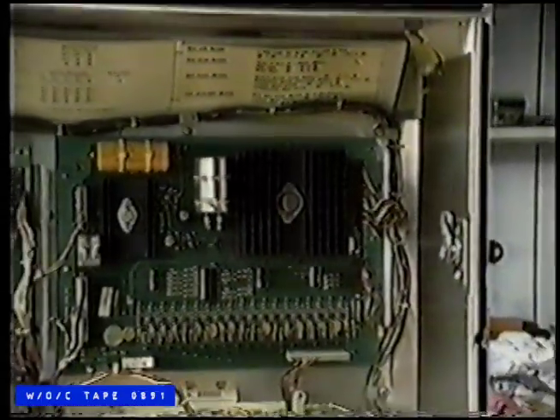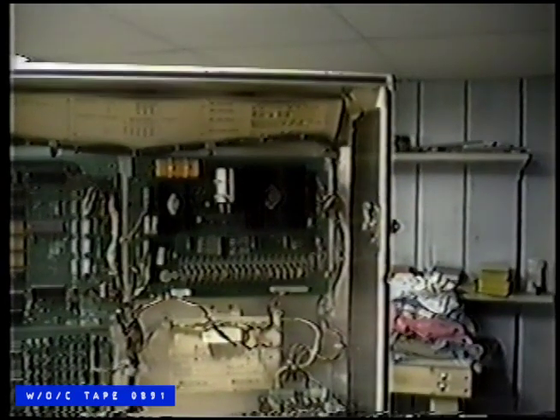So we're going to assume the problem is right here, we've got no power coming out of this A2 power board. What we're going to do now is some voltage checks right on here where they have the test points. We've completed that phase also, and we find that we're missing, or as low actually, voltage required by this power supply up here to give us our 5 volts. So now we're going to yank the transformer out of there and find out where the voltage disappeared to. That's the next step.